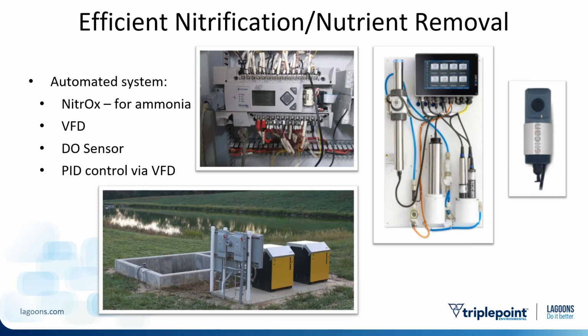But yeah, DO control on the effluent of an ammonia removal device will enable you to ramp your blowers up and down and ensure you're properly meeting the needs of the microbial organisms doing the removal for you, oxidizing those nutrients.